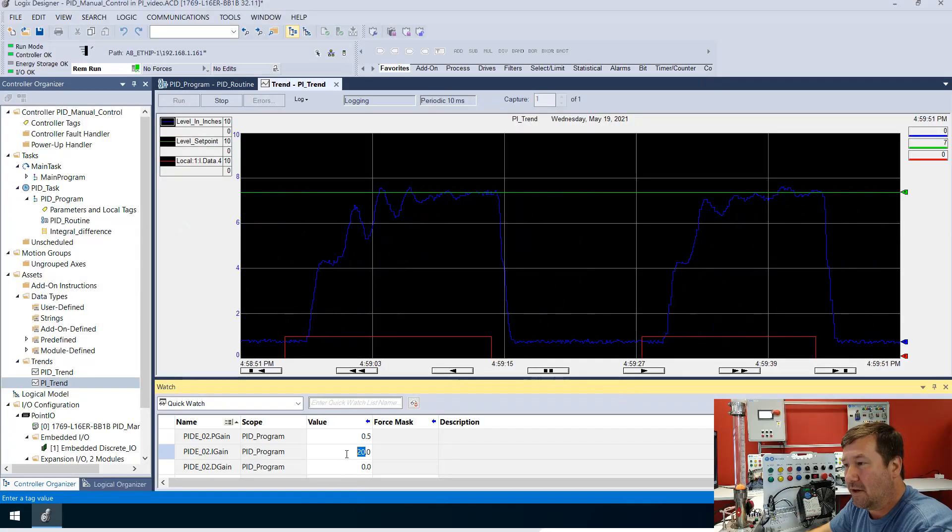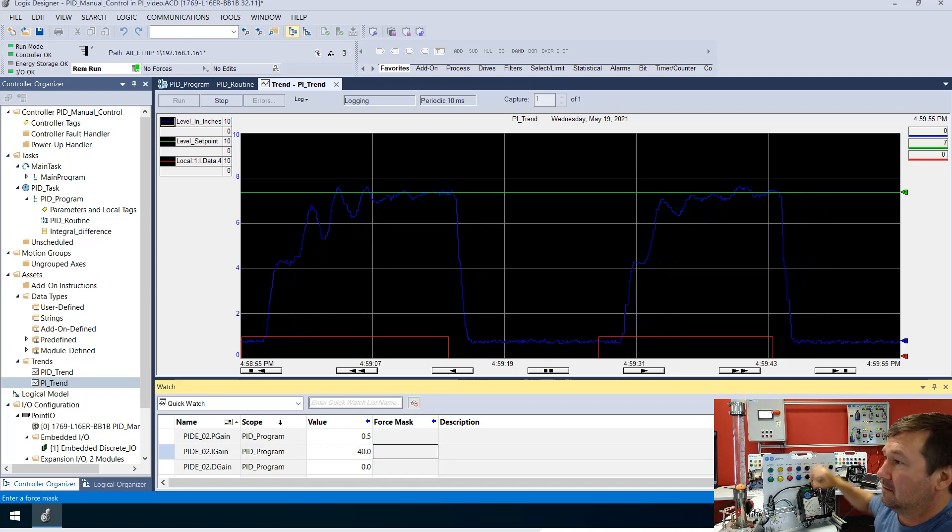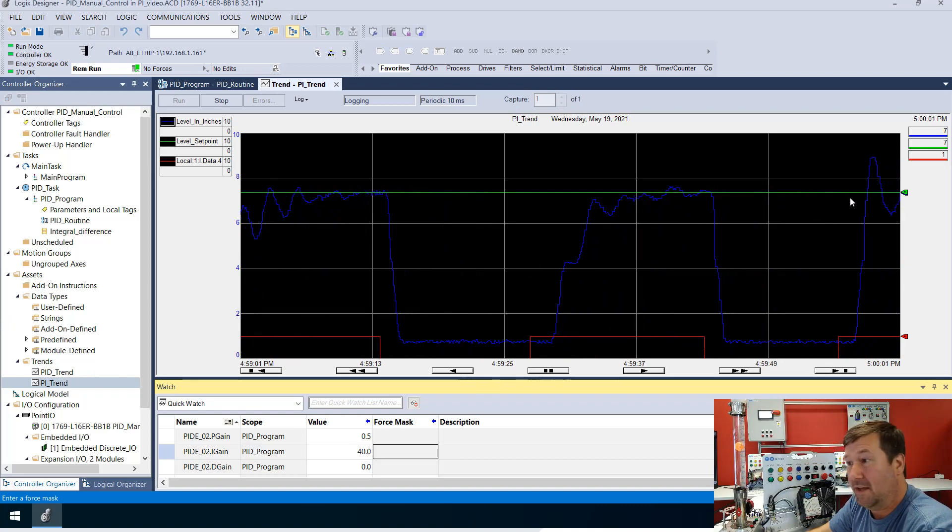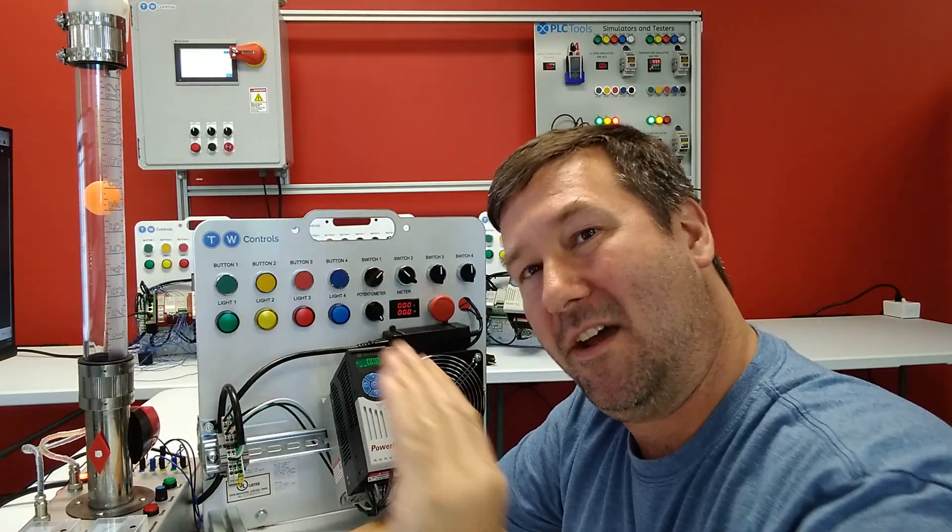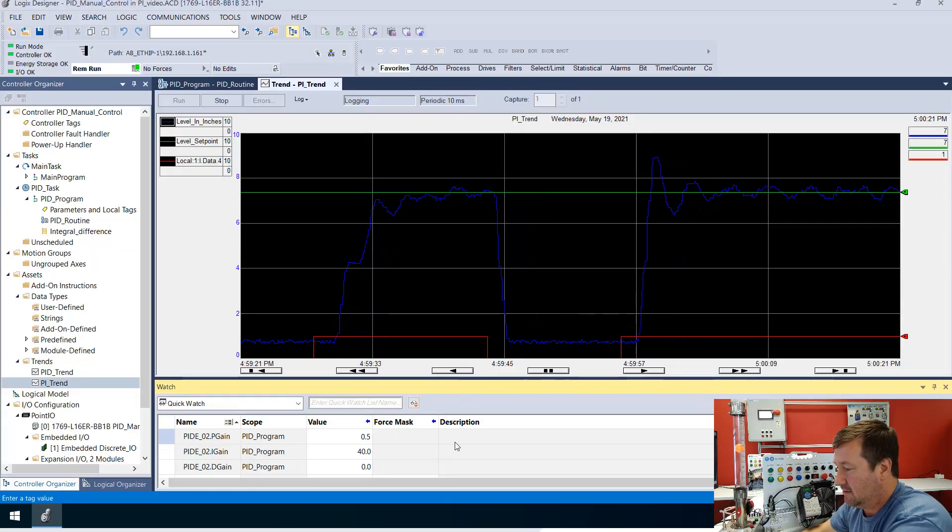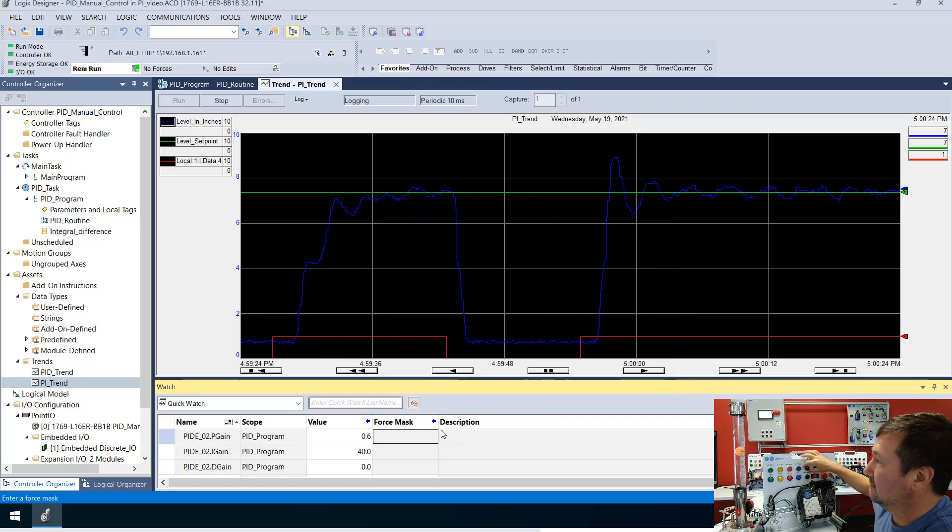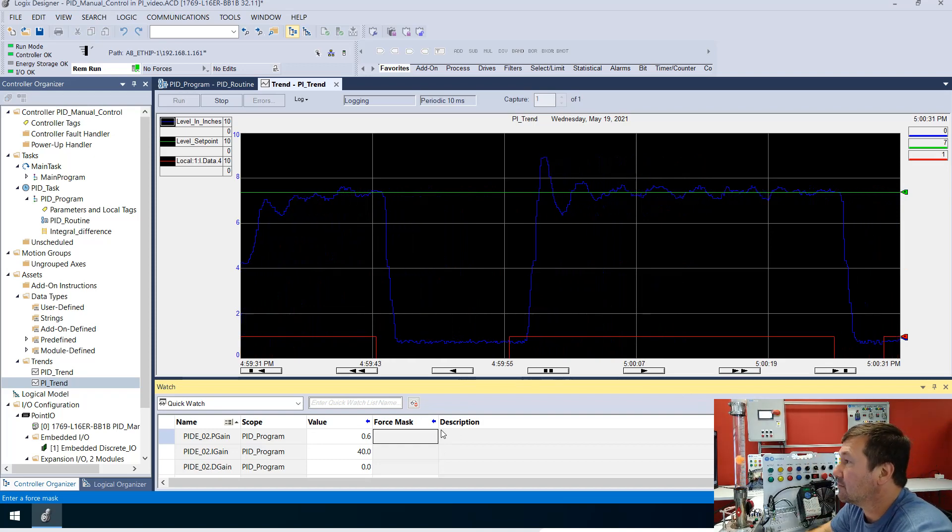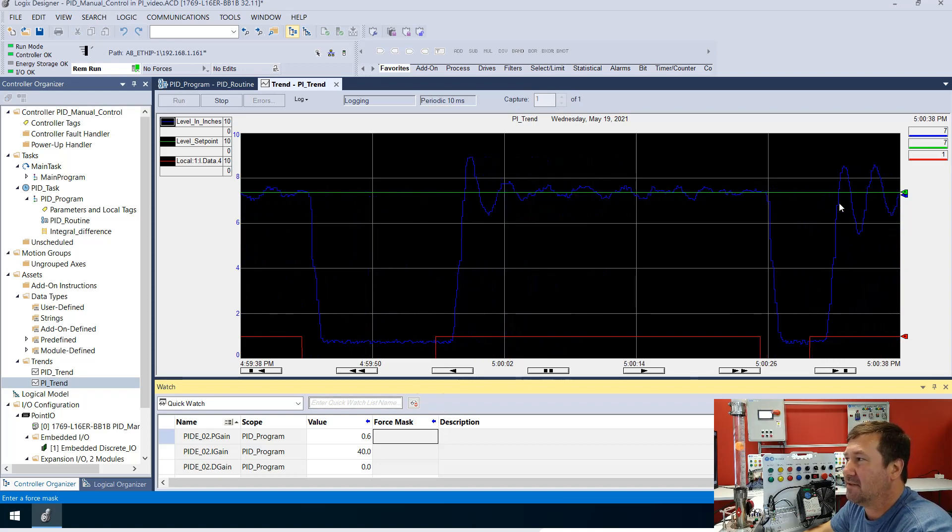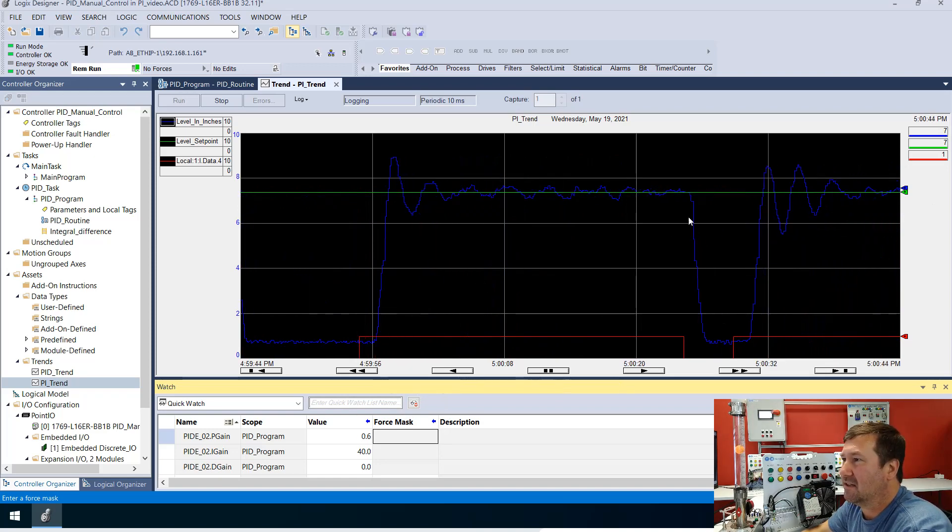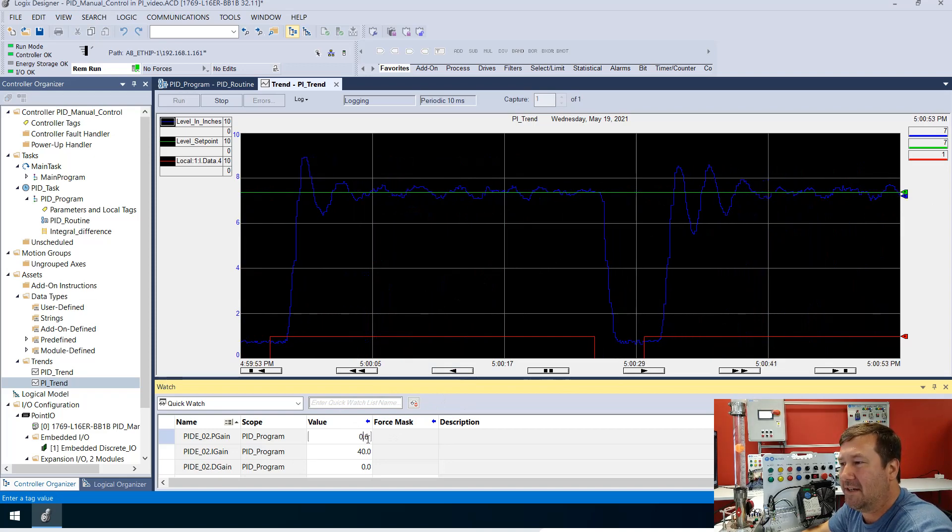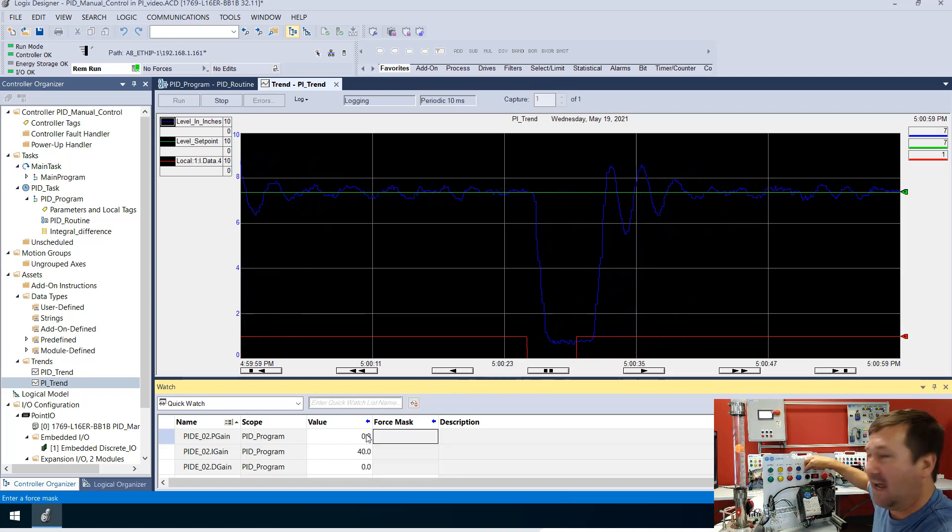Now let's try going the other way though. We were at 30 on our integral, we went to 20. Let's take it to 40. Now it shoots up much faster than it did with the 20, definitely, or the 30. But you see, we got a bad overshoot here. So we can use that proportional to stop that overshooting and kind of curve that error in. So let's bring our proportional up a little to 0.6. All right, so that is better. But we definitely have some oscillation going on here still. And yeah, we're going to need to lower that proportional. But we're starting to get some overshoot. So we're probably not going to be able to run this aggressively. But let's just try 0.8, just to see what happens.